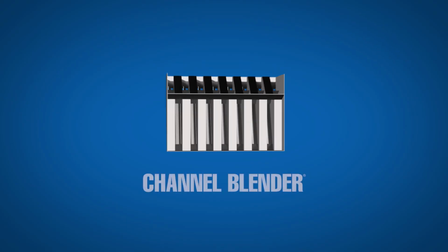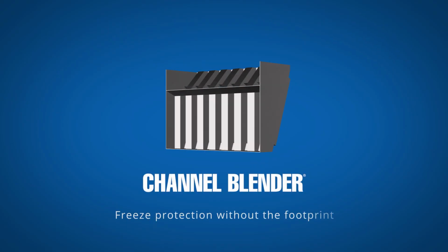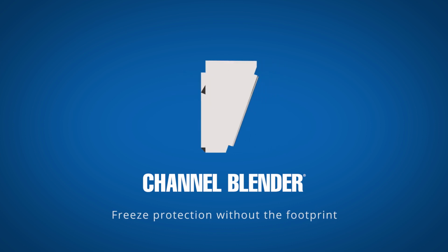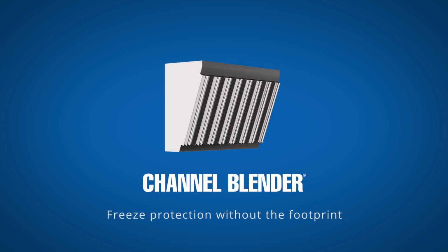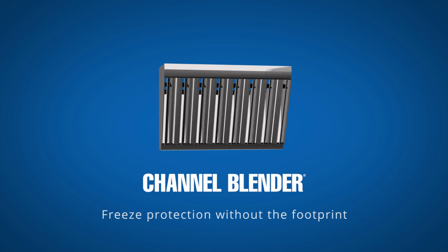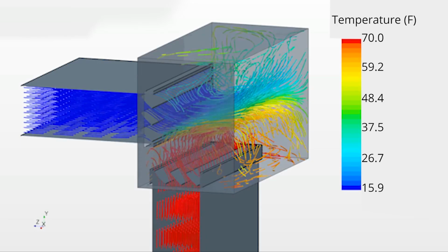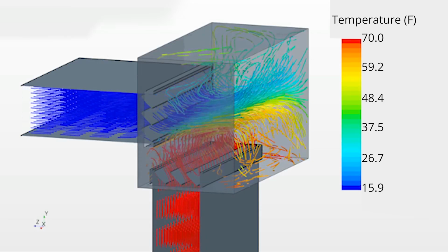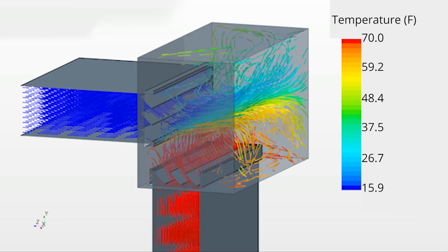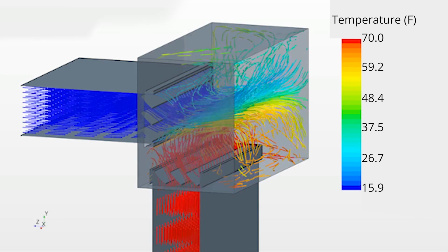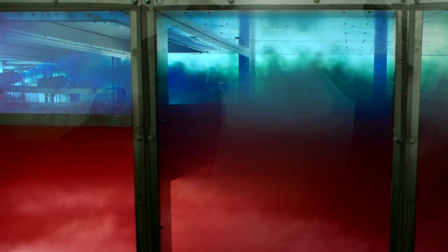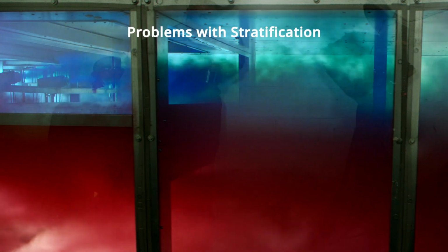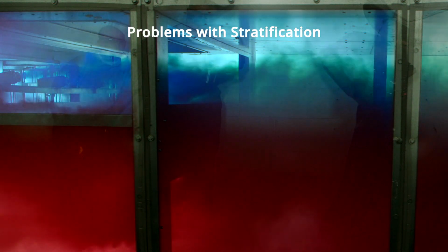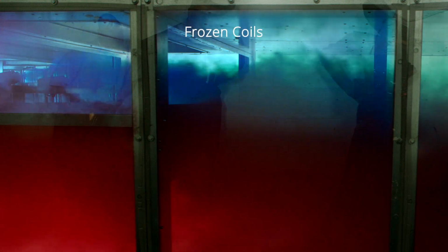The Channel Blender by Blender Products improves mixing box performance in air handling units without the space required with traditional static mixers. Temperature stratification is the result of cold outdoor air and warm return air failing to mix within the air handling unit's mixing box. This creates cold spots in the plenum that cause operating problems including freeze-stat trips and frozen coils.